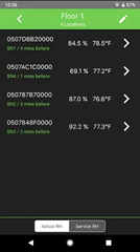In this list, you will see the most recent RH and temperature readings for each location and how long ago the readings were taken. At the bottom of the screen is the indication of whether these are actual readings or those estimated when the building is at service temperature, according to the service temperature settings specified for this sensor map. To view the estimated in-service condition RH and temperatures, press on the Service RH to the right of the actual RH at the bottom of the screen.